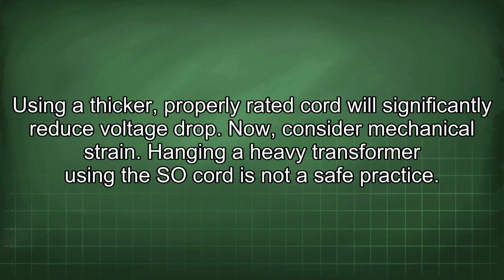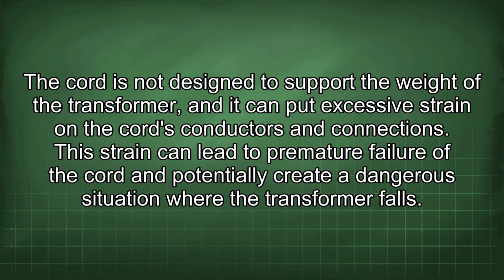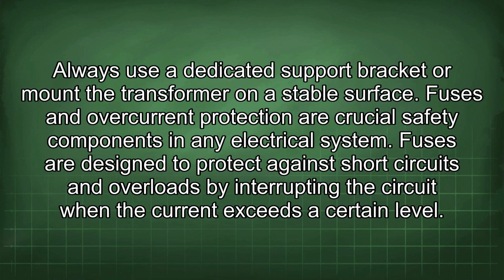Now consider mechanical strain. Hanging a heavy transformer using the SO cord is not a safe practice. The cord is not designed to support the weight of the transformer, and it can put excessive strain on the cord's conductors and connections. This strain can lead to premature failure of the cord and potentially create a dangerous situation where the transformer falls. Always use a dedicated support bracket or mount the transformer on a stable surface.